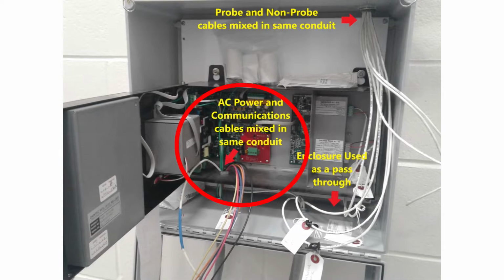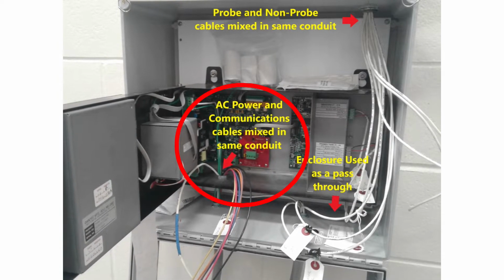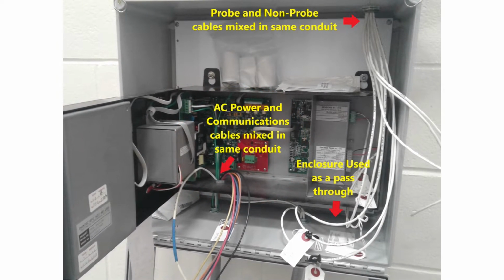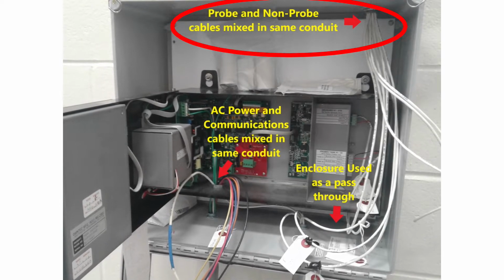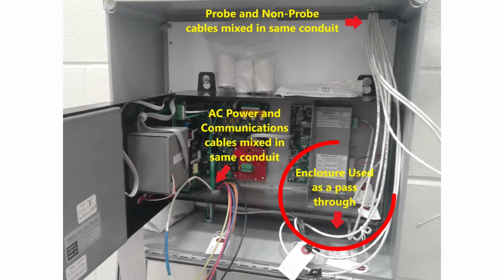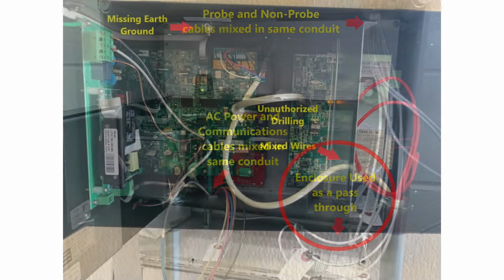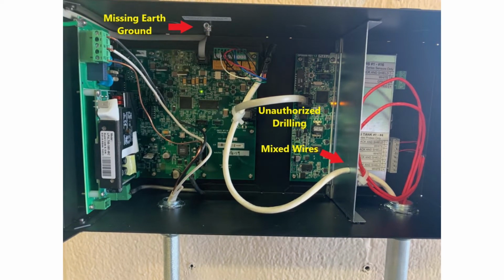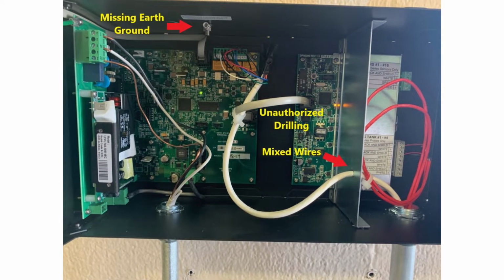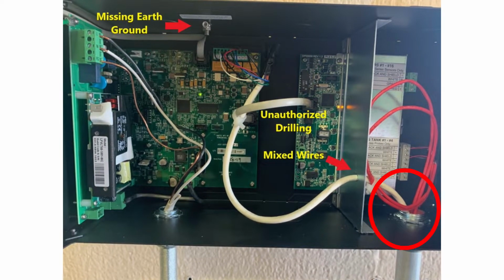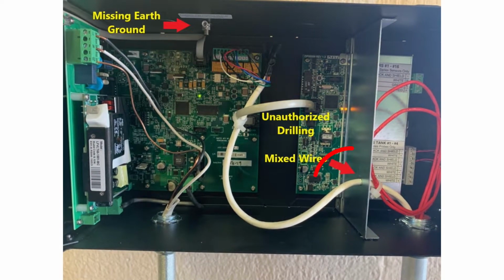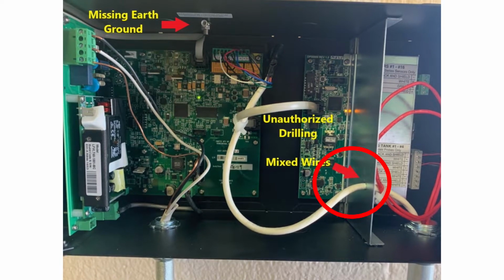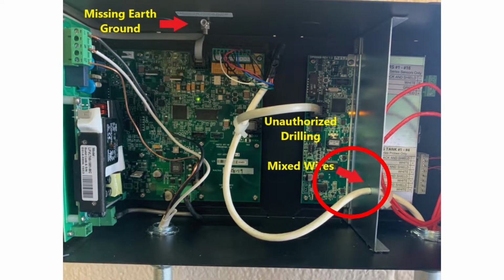The AC power and the low voltage communication lines are mixed in one conduit. Probe and non-probe cables are mixed in one conduit, some of which just passed through the enclosure. This was another installer trying to save on the number of conduits used. The probe and low voltage cables were mixed in one conduit, and a hole was drilled in the intrinsic barrier to pass the one cable to the non-intrinsic side.